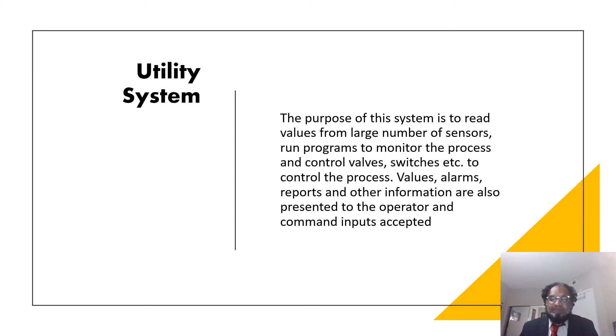A process control system is used to monitor data and control equipment on the plant. A very small installation may use a hydraulic or pneumatic control system, but large plants with up to 250,000 signals to and from the process require a dedicated distributed control system, also known as DCS control system. The purpose of this system is to read values from a large number of sensors, run programs to monitor and control process valves, switches, etc. To control the process, values, alarms, reports, and other information are also presented to the operators, and command input is accepted.